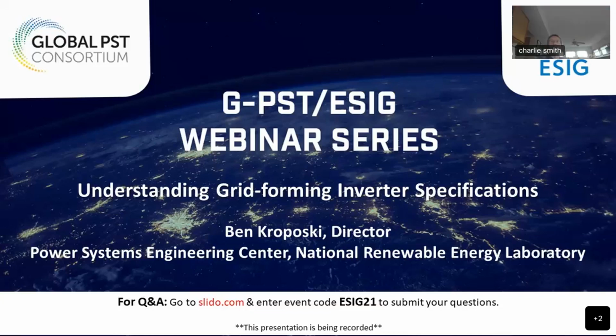Okay. Another one on controls. In a PV plant, how does the grid forming control interact with the maximum power point tracking algorithm that has already been developed by the vendors? Yeah, well, the maximum power point tracking algorithm, it depends which type you have. Again, it depends what type of max power point tracking algorithm you've deployed in your system, but that's really, obviously changing the DC input side control, whereas a lot of the functionality that we're talking about is the AC output side.